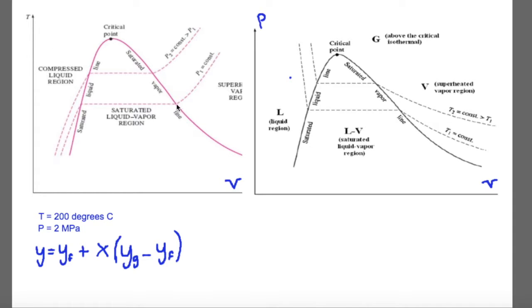And then we get to this area here, and what happens when you get to the saturated vapor line is that it's pretty much all vapor at this point. So any additional heat added to the system will result in what we call the superheated vapor region. That means it's been superheated. So, again, I'll just recap everything. We're going from liquid to liquid and vapor to superheated vapor.